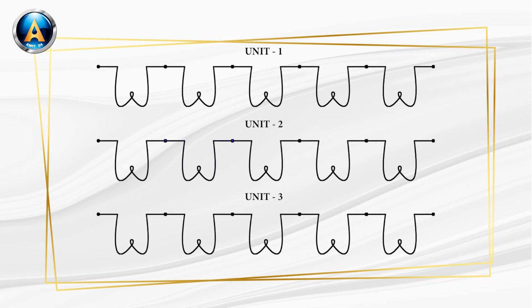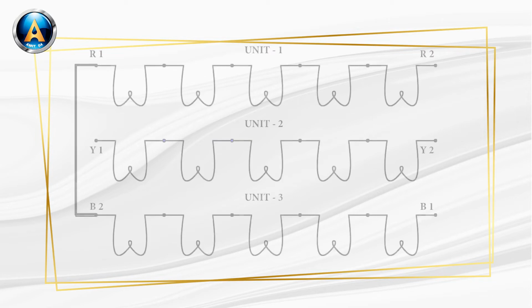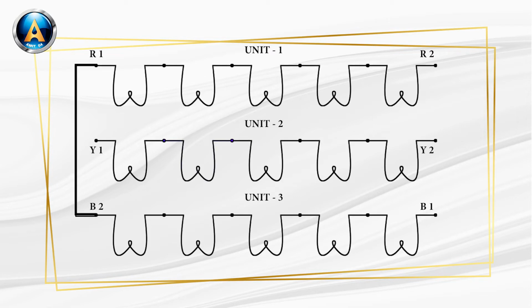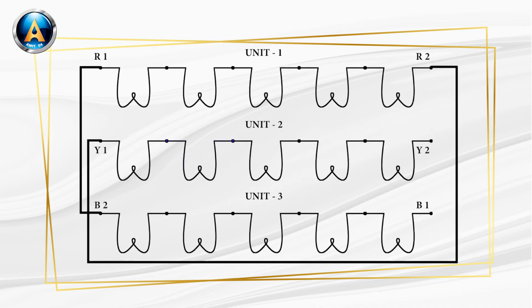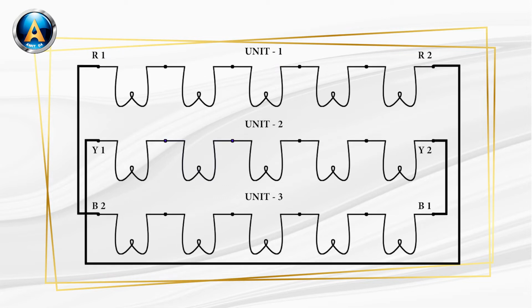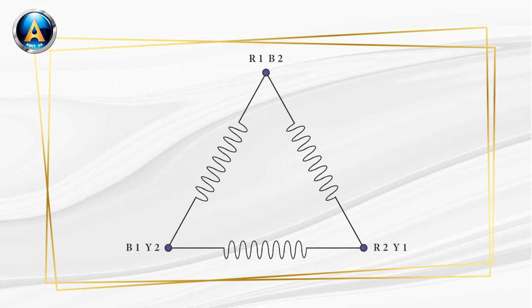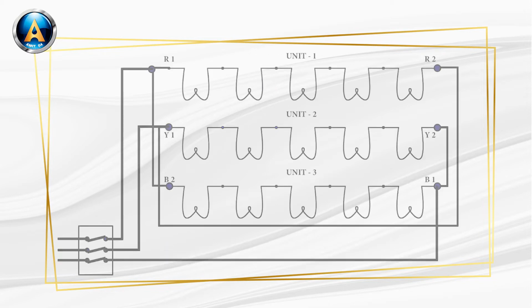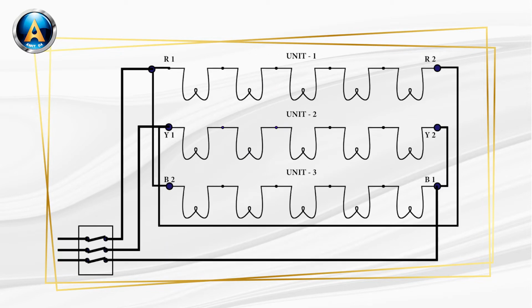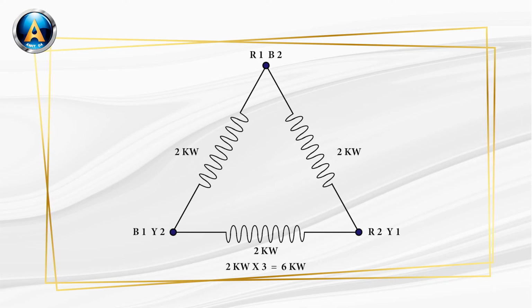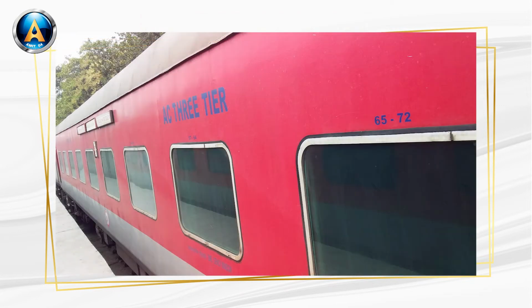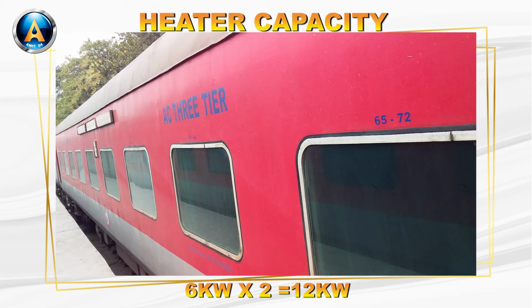There are 3 sets of units connected to each other like this. R1 terminal is connected with B2 terminal, R2 terminal is connected with Y1 terminal, and finally Y2 terminal is connected with B1 terminal like a delta, and the 3-phase power supply is connected like this. So the total wattage of the delta connected unit is 2 kilowatt into 3, that means 6 kilowatt. And for heating of air inside the LHB AC coach, a total of 6 kilowatt into 2 is equal to 12 kilowatt heater is required.